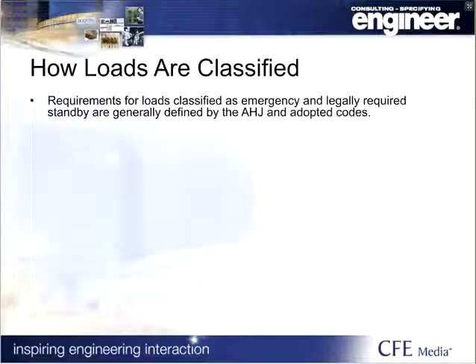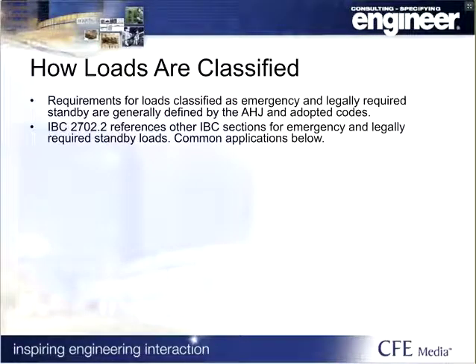Here we'll look at a few examples of how some codes define the types of loads that are connected to the emergency and legally required systems. As mentioned earlier, IBC 2702.2 defines the type of power, emergency or standby, for several key loads that are important to the safe evacuation of building occupants as well as those that aid in rescue efforts.